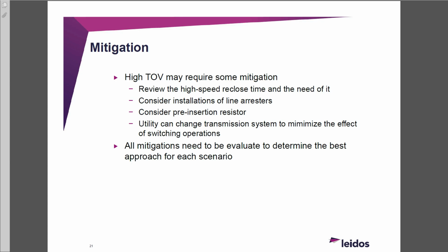One of the major reasons they're getting close to these lines is for line control after a fault operation. If you have lightning and automatic reclose, I go out to patrol the line, it's a 70-mile long transmission line. I don't know many utilities that send an operator to the other side of a 70-mile line and cut out and close to do their line control.